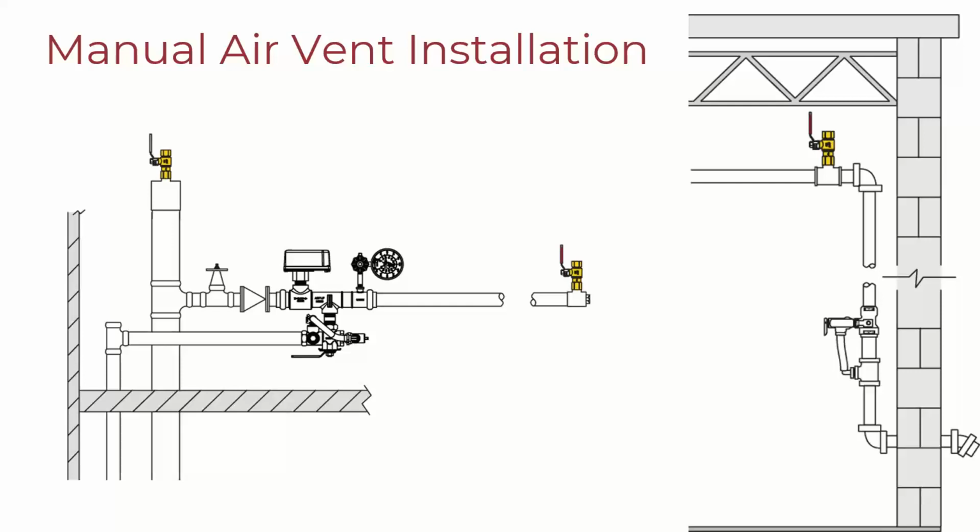Again, the whole goal of having a manually installed valve is to make sure that every time the system is serviced, which would introduce new air to the system, those manual valves are opened to release any trapped air that comes in.